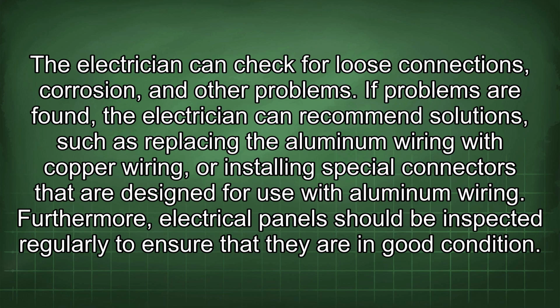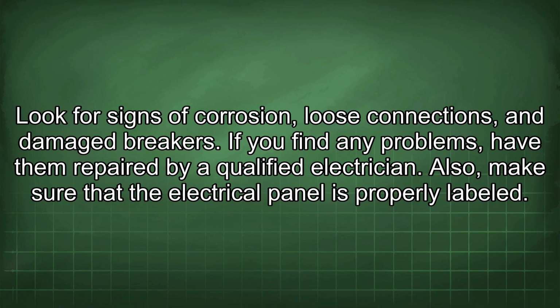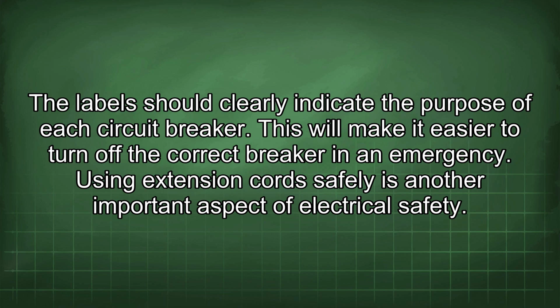Furthermore, electrical panels should be inspected regularly to ensure that they are in good condition. Look for signs of corrosion, loose connections, and damaged breakers. If you find any problems, have them repaired by a qualified electrician. Also, make sure that the electrical panel is properly labeled. The label should clearly indicate the purpose of each circuit breaker. This will make it easier to turn off the correct breaker in an emergency.